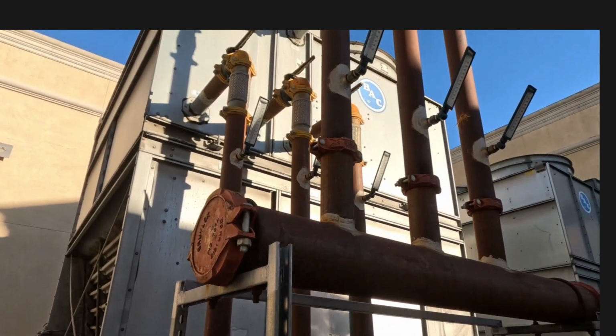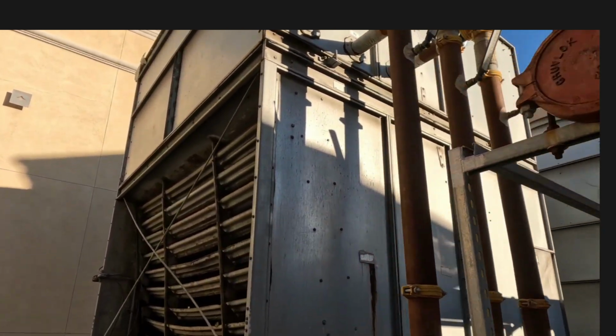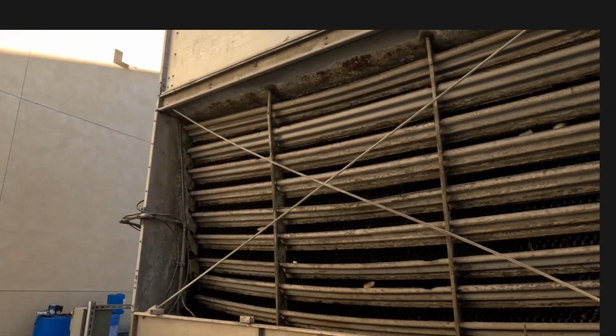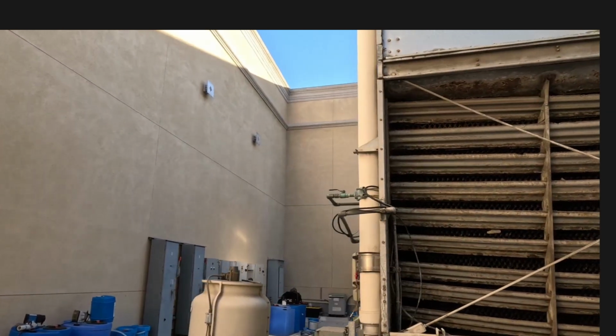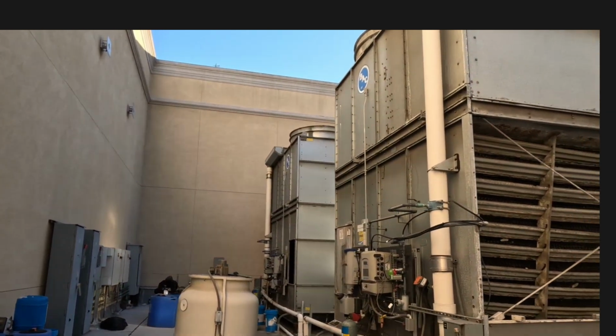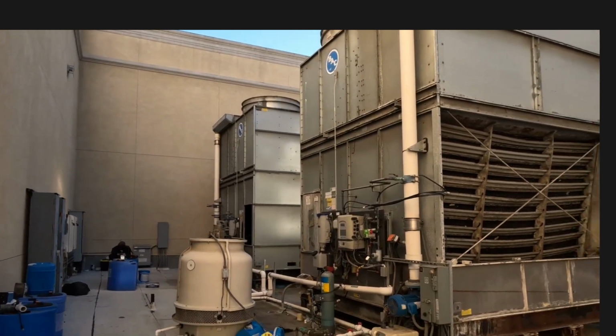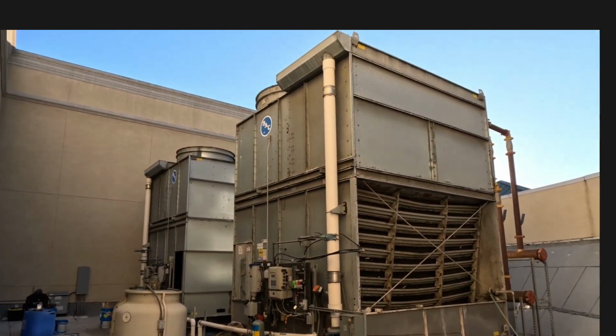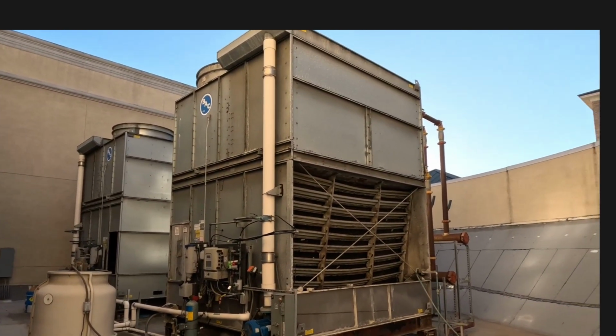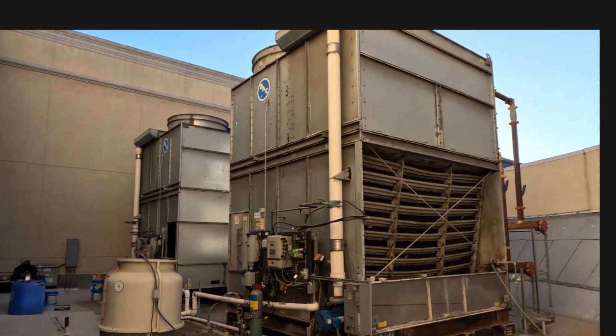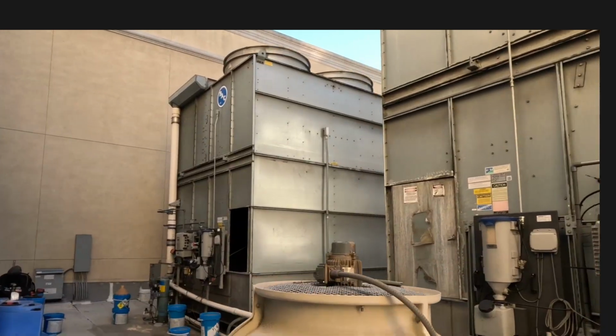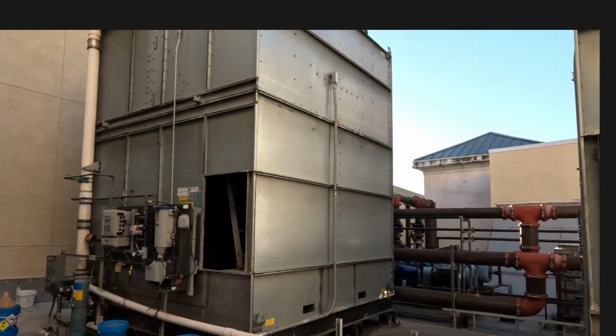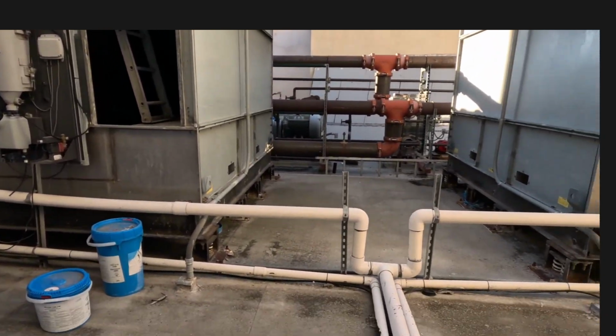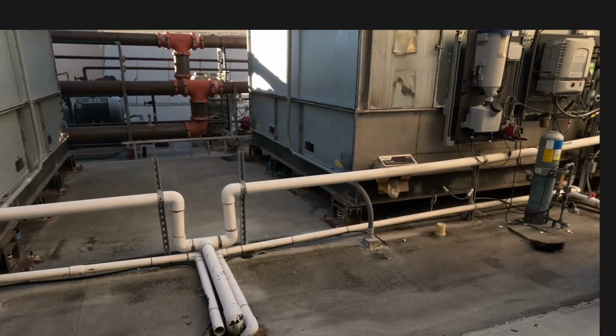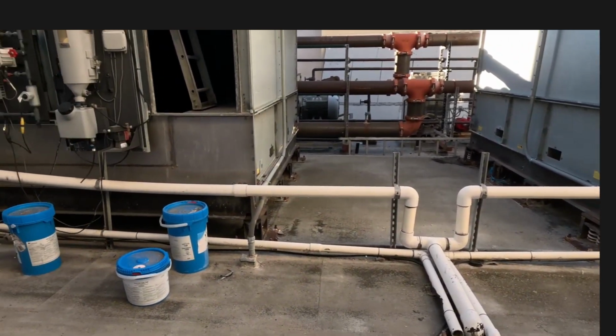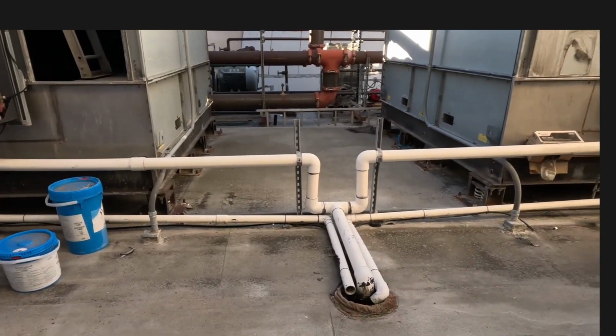Got thermometers and everything, same as the other cooling tower. But in a nutshell, I just wanted to go over this cooling tower, or I'm sorry, closed loop cooling tower or fluid coolers. In order to get up top, you do need to put an extension ladder up. I'll show you guys what size extension ladder we need to put up here. And it goes to a common drain, so both drains from these towers are connected down to this common drain.